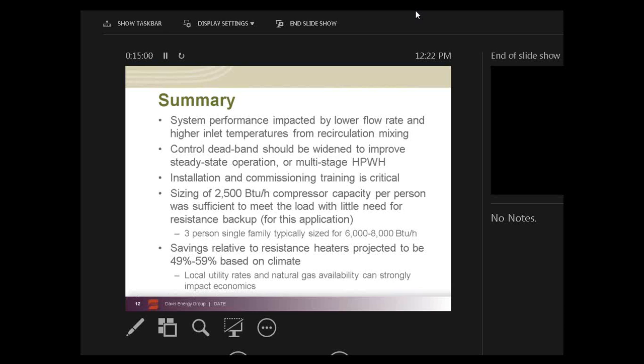Installation and training is critical. These contractors had not had much experience with heat pump water heaters, and there was not at the time adequate feedback to alert maintenance of unit failures. That was later remedied. But had the unit been in service and not monitored, it would take months for operators to notice the failures in the utility bills.